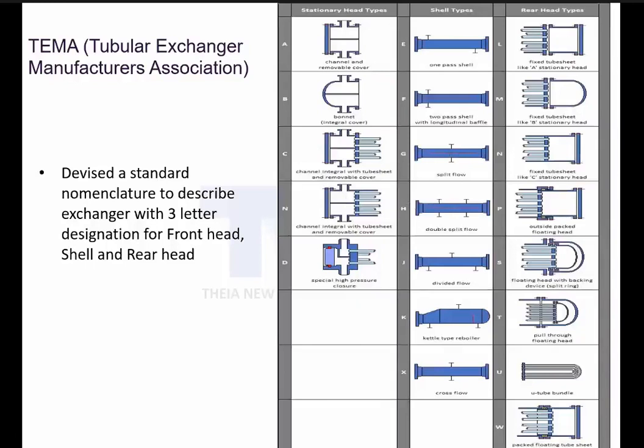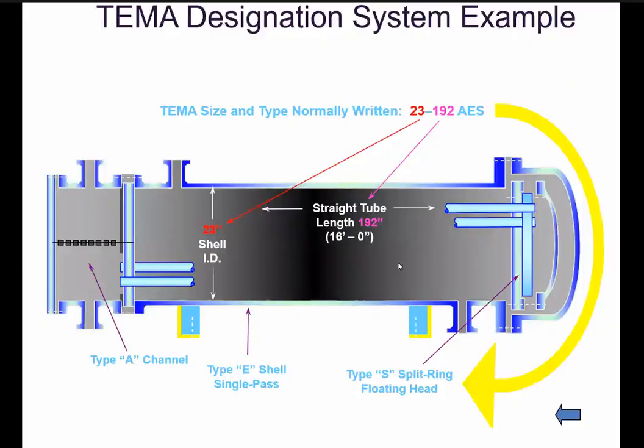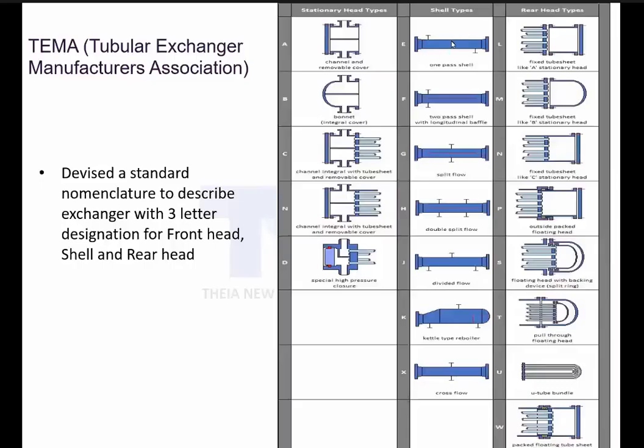Okay, so H type and G type are thermosiphon horizontal. I'm talking about horizontal. Then there is another type called the J type. J type is used when there is more shell side pressure drop than E. The E shell is mostly preferred first. If the pressure drop on the shell side is more than E shell, then the next option is J shell.